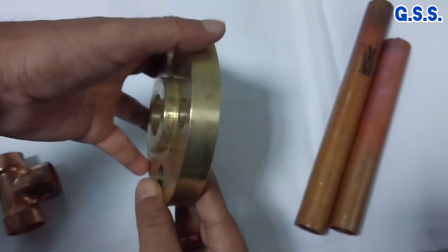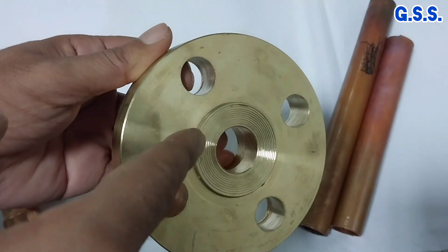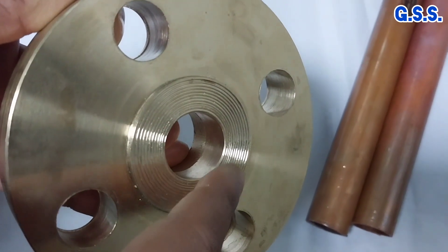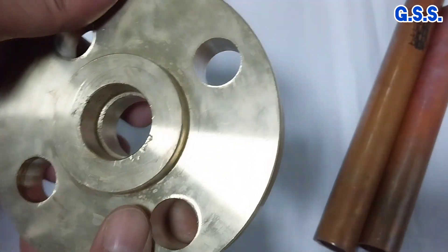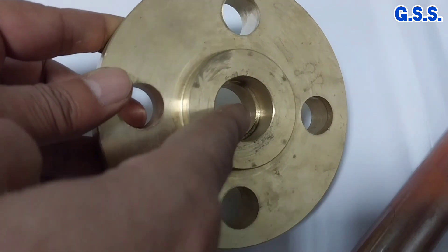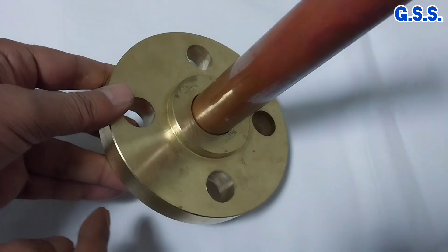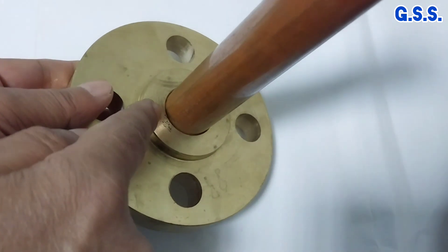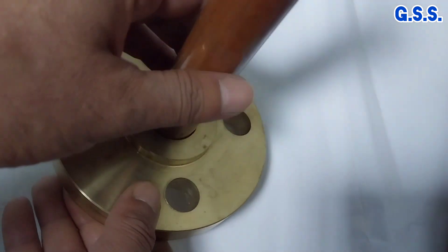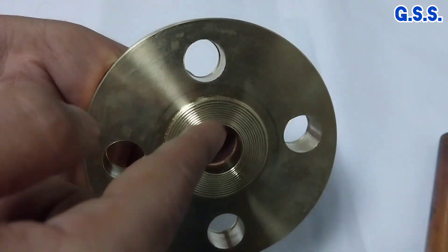Usually this type of cast brass flanges are used in copper piping. Brass is as per BS1400HTB1. This side of the flange has a raised face with serration, and the other side of the flange has a socket where copper pipe is inserted. Then silver brazing is done between the copper pipe and brass flange on the entire socket surface. The socket ID of the brass flange should match with the copper pipe OD.